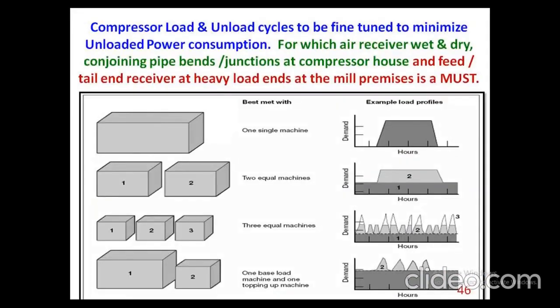The cut-in cut-out, this is more important. If you have a batch of compressors, 1, 2, 3 or 1 and 2 only, operate the base load at full condition, and modulating load only for the 30%. The VFD will be on the modulating load only. Base load will be running full, and for the modulation, say 20 to 30%, the VFD will be put into action. In fact, by adjusting the cut-in cut-out for the given textile mill, this itself can give energy savings within 1 to 2 hours. The mill can save by fine-tuning the cut-in cut-out parameters for the given compressors. What is to be set to 6 to 6.5, what is to be set to 6.2 to 6.7, all this matters depending on the loading and the application.